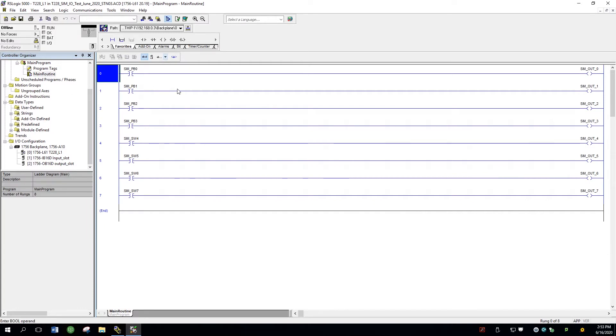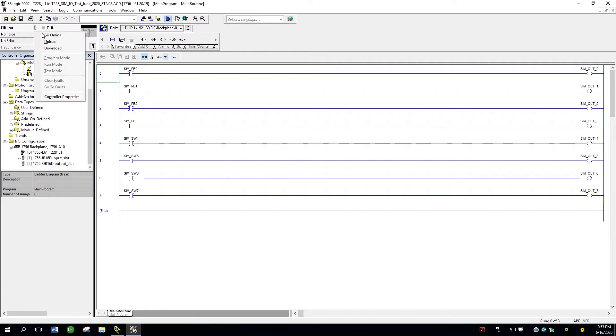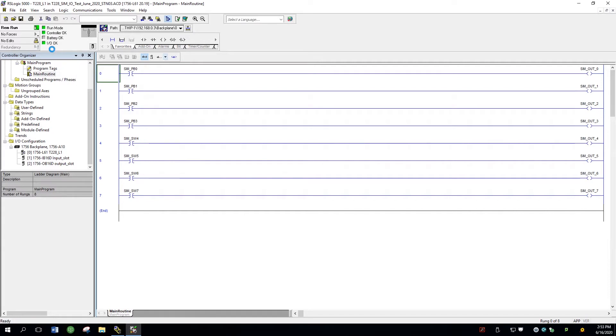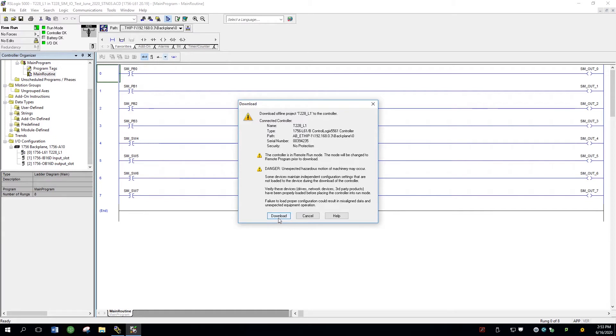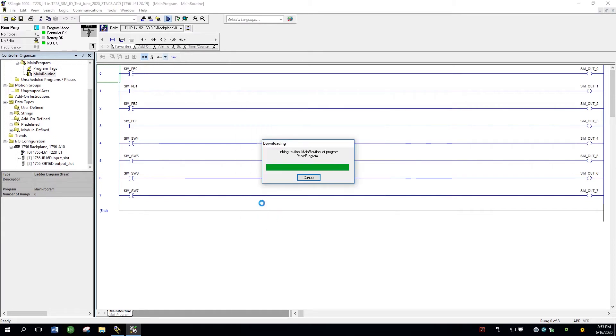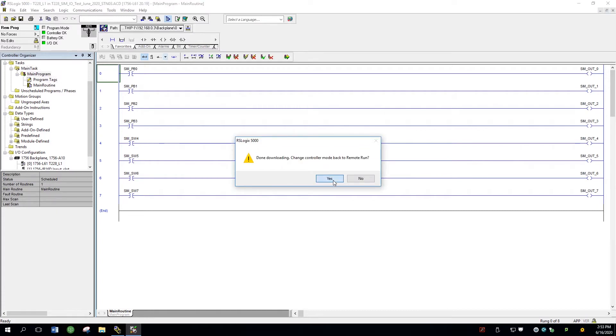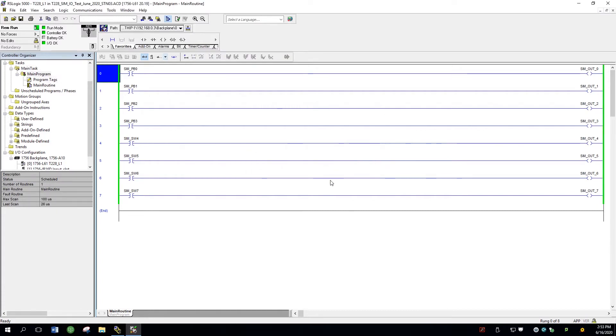I'm just going to verify that you can actually run this, and we can test it out as well. So you have to go into where it says Offline, click on this tab, and go to Download. Click on Download. You should see this green bar moving along. Select Yes when that occurs, and just verify that it's in Run Mode. You have three green boxes here — the I/O is okay, the controller is okay, and we're in Run Mode.